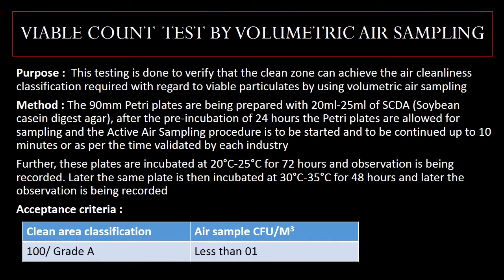The last but most important qualification test is the viable count test by volumetric air sampling method. This testing is done to verify that the clean zone can achieve the air cleanliness classification required with regard to viable particulates using volumetric air sampling. During execution, 90 mm petri plates are prepared with 20 ml to 25 ml of SCDA (soybean casein digest agar). After pre-incubation of 24 hours, the petri plates are allowed for sampling and active air sampling is started and continued for up to 10 minutes, or as per the time validated for each industry.